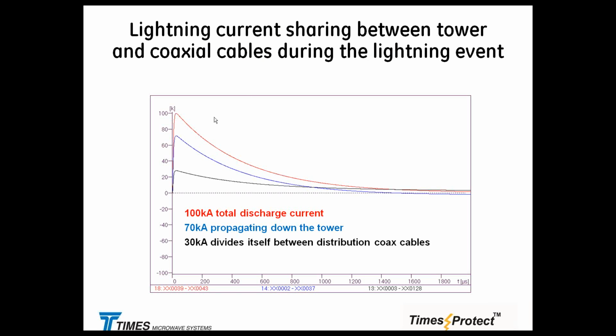The good thing that works for us is that the tower, because of its massive size, in a well-grounded tower environment will take in the range of 60 to 70% of the current down. If you look at a monopole or three-legged tower, we have the J-bolts holding everything into the foundation, and the rebar inside that is very well connected. So that tower is going to be the best conductor we might have. The question is, what are we going to do to enhance that in the soil around the tower? I have a slide to show you later on.